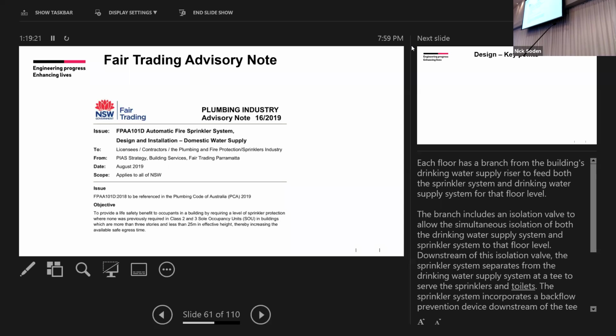Why was it put in there? Dead leg, to make sure we didn't have a dead leg. There's a requirement in 101D to minimise dead legs, and that was agreed by the water supply authorities. So when you're designing a system and doing your layout, you've got to minimise it. I forgot what the number is, but there's a number in 101D to minimise that. The water supply authority said, if you keep it to that, that's fine. If you have a dead leg less than that, then we're good to go.